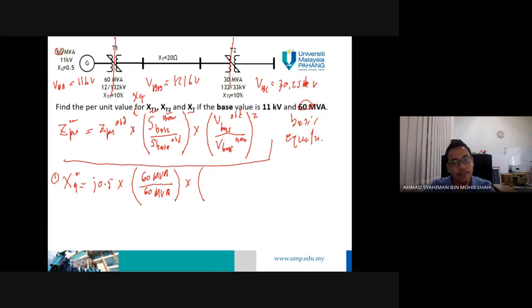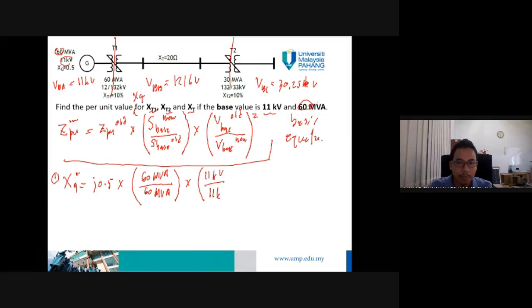Multiply with the V base old. V base old is the original V base for these components, 11 kV. Then, new is also the same 11 kV, squared. So at the end you get the same value. This means all the components must be calculated in per unit based on this method. Coincidentally, the base voltage and base MVA for XG are also the same, so XG remains the same, J 0.5.